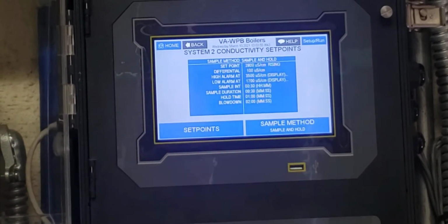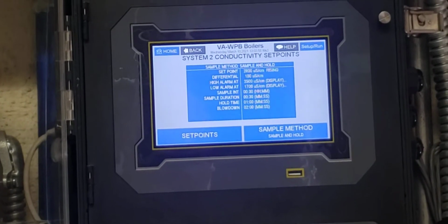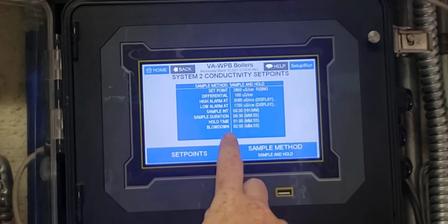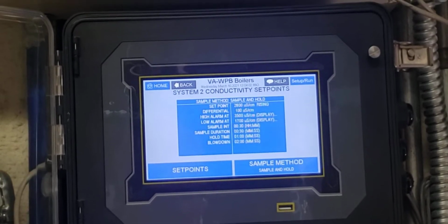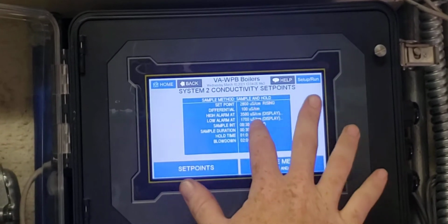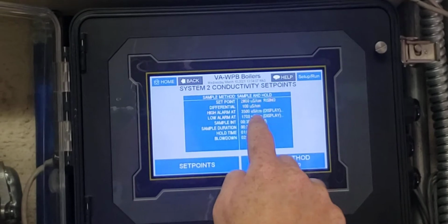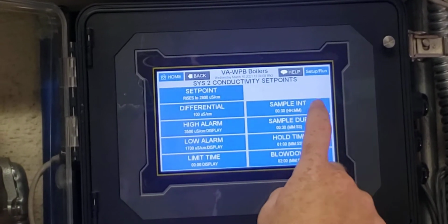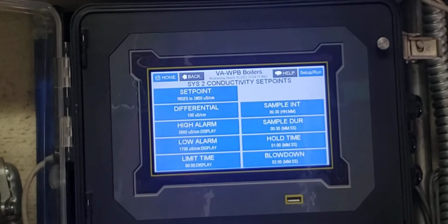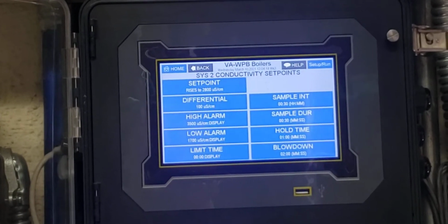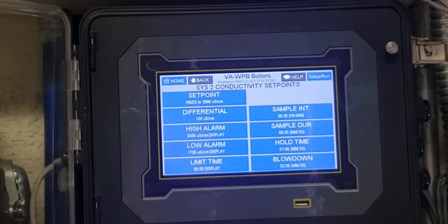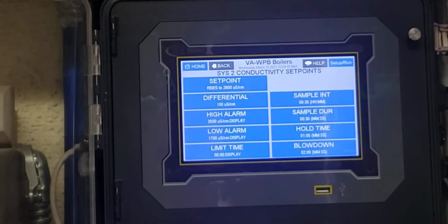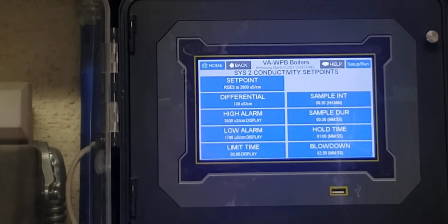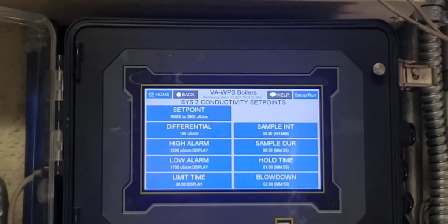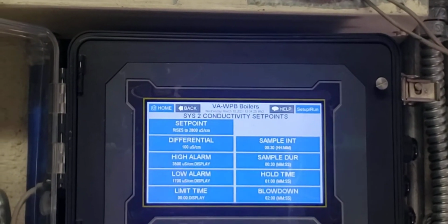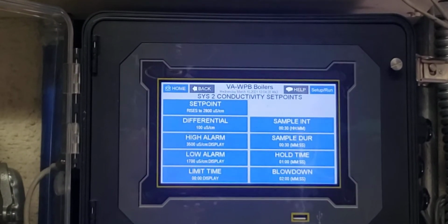See, like this one, we must have been messing with it. The sample interval is set for 30 seconds instead of 15 seconds. So just to keep it the same, I'm going to go into set points. And see, I changed that when we were having issues with blowing down and the conductivity wasn't matching right. Yeah, and remember we were sticking the actuator. Oh, the actuator was getting frozen, yeah, and I was thinking it was the sample time.